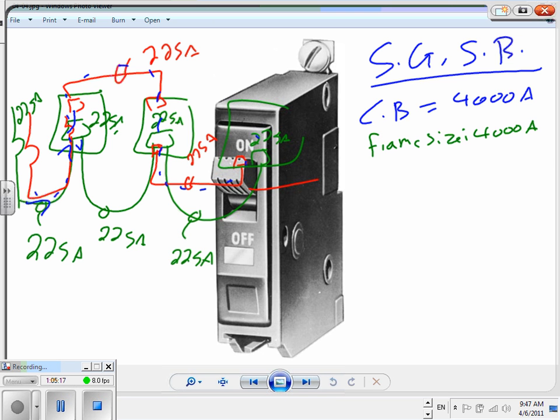Now, what is the frame size? Frame size is how big a physical space I need for the circuit breaker. That big. And most of the time, guys, 3,000 and 4,000 amp circuit breakers fit in the same slot. So the frame size is 4,000, meaning I can fit up to 4,000 amp in this slot. Okay, that's just the physical size. The second one is sensor size. Anybody can guess what the sensor size is?